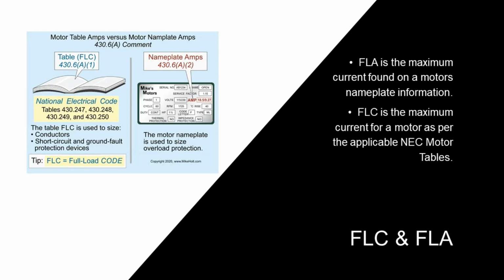All right. I know we're not really going to discuss motors this year, but this is an imperative thing for you to understand when anyone's talking about FLA and FLC. FLA is the maximum current found on motor nameplate information. FLC is the maximum current of a motor per the NEC motor tables. So I want you to think of FLC for code book and FLA for actual. We're going to get the numbers out of the code book for the C, and we're going to get the actual numbers off the motor for the A.